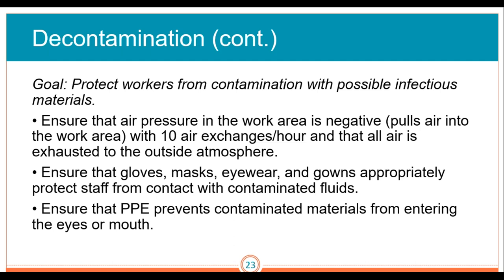Decontamination: our goal is to protect workers from contamination with possible infectious materials. We want air pressure in the decontamination work area to be negative — negative — with 10 air exchanges per hour, and all air exhausted to the outside atmosphere. We want to ensure that gloves, masks, eyewear, and gowns appropriately protect staff from contact with contaminated fluids. It gets hot in decontam — it can be a bit of a workout.